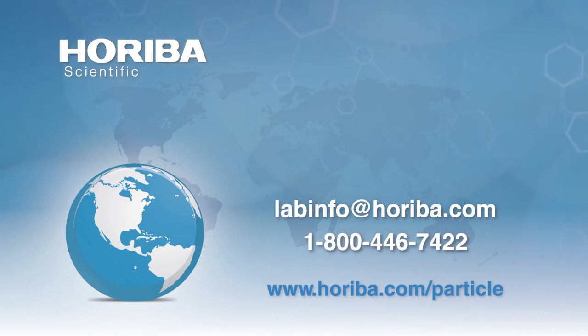Did I answer the question? Yes. Thank you. Next question is for Jeff. When using a cell with a paste, paste cells. Oh, I'm sorry. Let me backtrack. When using a cell with a paste, are there any issues with the sample reacting with the cell? And second part to the question is, are cells made with different materials? Yeah. So the cells we offer are glass, and it escapes me at the moment what grade glass they are. The wetted materials for the HL cell would be glass and either a Teflon or aluminum ring around the cell. And for the paste cell is just the two glass plates. Yeah. So if you have something that's very, well, if you have something that reacts with glass, then that will become a concern quite quickly. Particularly since we have a highly loaded sample. But most materials I've seen, we have not had that issue come up. Thank you, Jeff.